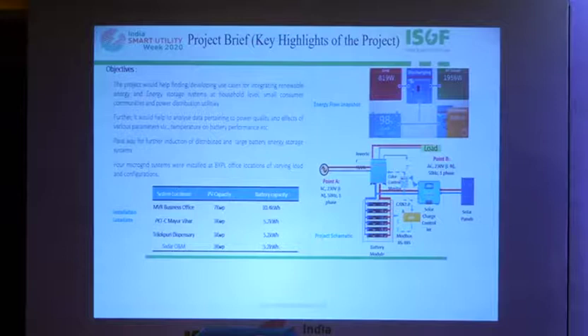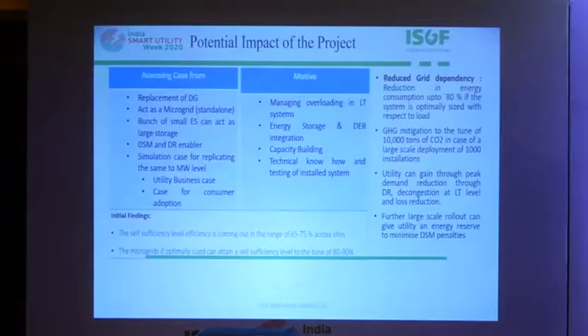Here, we have especially designed this inverter, which can communicate with the solar and grid energy level, and can determine what kind of loading is required to meet the load, and when charging or discharging should happen. So this system can be a replacement for DG systems in Delhi, especially given pollution issues. This system can act as an islanding system itself, acting as a microgrid.